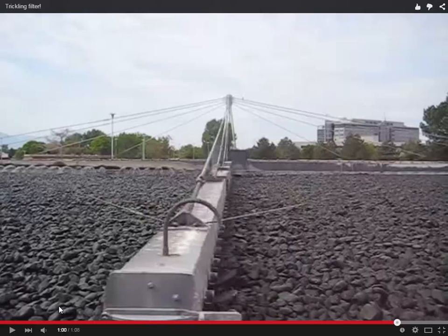The way they get their air, in a lot of cases, like in this case, is that there's no external blower. It's just natural passive ventilation going up through the rocks. So if it was continuous spraying, it wouldn't get the same opportunity on the surface of those rocks to be in direct contact with air.